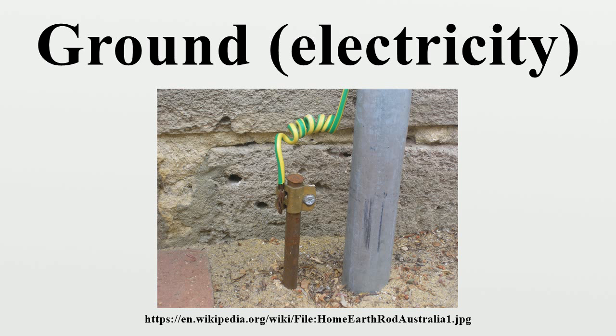Equipment bonding conductors provide a low impedance path between non-current carrying metallic parts of equipment and one of the conductors of that electrical system's source, so that if a part becomes energized for any reason, such as a frayed or damaged conductor, a short circuit will occur and operate a circuit breaker or fuse to disconnect the faulted circuit. The earth itself has no role in this fault-clearing process, since current must return to its source. However, the sources are very frequently connected to earth. By bonding all exposed non-current carrying metal objects together, they should remain near the same potential, thus reducing the chance of a shock.